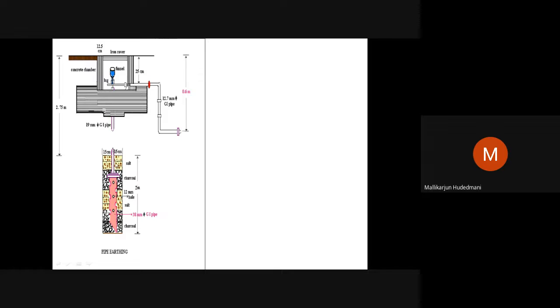Then you have to bury inside a 38 mm diameter galvanized iron tube. This is actually a pipe, a galvanized iron pipe laid down. Before laying it down, the edge is conically cut, the corner cut, and a number of holes are marked on the body, meaning through holes are provided. Then it is buried inside the hole, the deep slot cut by the construction fellow, with alternate layers. You can see here a 15 centimeter layer of charcoal and salt. Charcoal and salt are assembled in the form of layer 1, layer 2, layer 1, layer 2 around that GI tube. As you can see here, 15 centimeter this side, 15 centimeter this side.